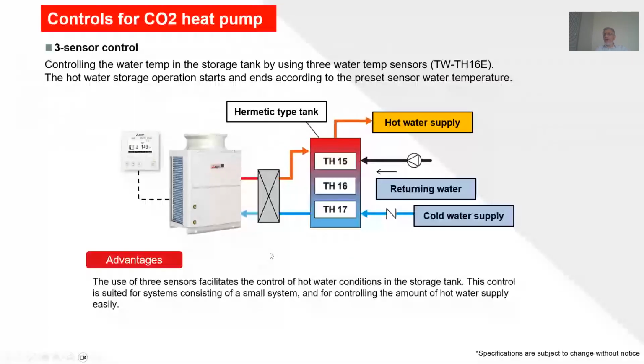As for how it works, you have options for control philosophies. You can have multiple sensors installed in your storage tank. If you're looking for a large demand of water, you can set the temperature at TH16 to 65 degrees centigrade. When the temperature of the tank at TH16 is 65, you shut down the machine, and once it goes lower than this, you start the machine.